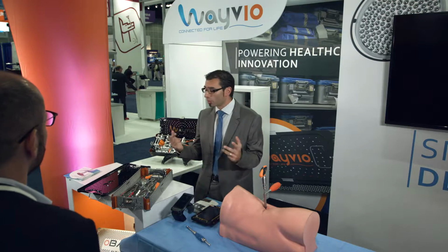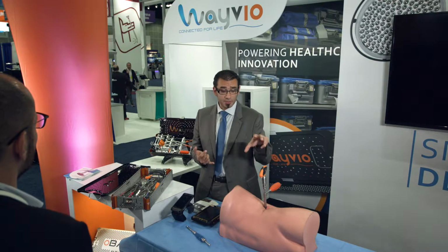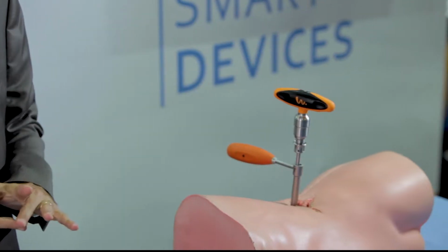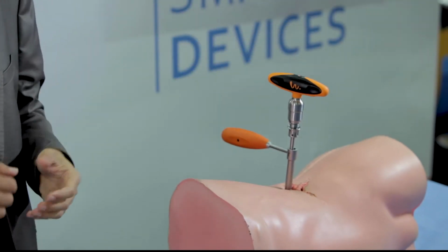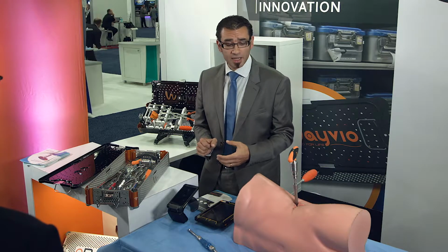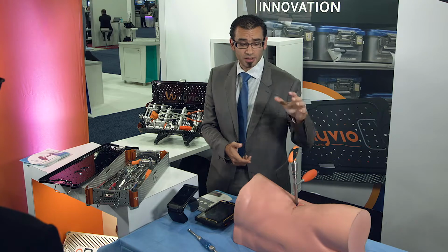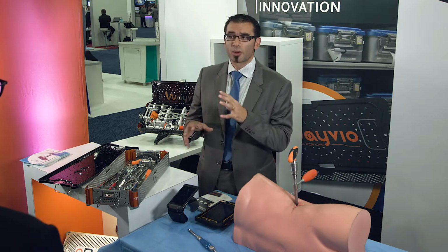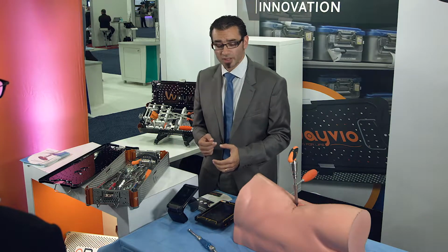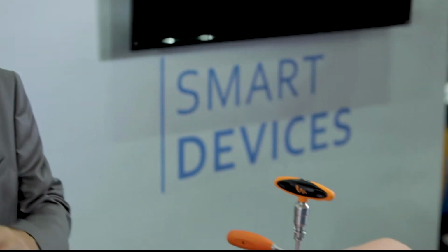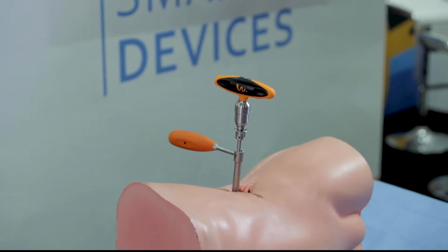to be sure that those trays are always rotating the most they can. All right, so today, aside from identification and tracking, you will get the number of times the whole tray is sterilized, the number of times one single instrument is sterilized, the number of times the torque limiter effectively releases, and also if I let the torque limiter fall on the ground, it will count that as an inadvertent event or use. The next step is having this technology integrated in most of our instruments at In'Tech Medical.